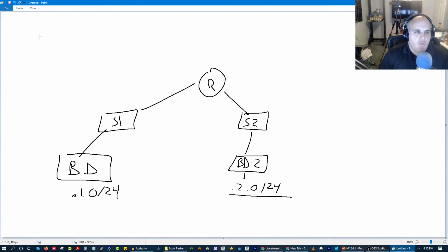Now, how BACnet works is it uses 2 broadcast services, and then the rest of its services are primarily unicast and multicast, meaning they're one-to-one or one-to-many, whereas broadcast is one-to-all. So the 2 broadcast services are the Who-Is, I-Am, and the Who-Has.